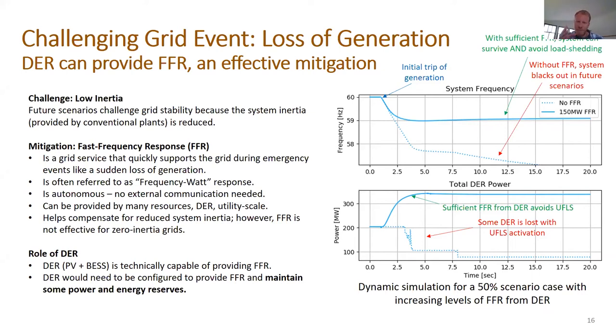In order to illustrate this, Joe, if you look on the right, there are two traces, and we'll just focus first on the blue dotted trace. This is one of the challenging scenarios we studied where there was a sudden loss of generation, which sends frequency down from 60 hertz, plummeting quite quickly over the span of a handful of seconds. You can see that the dotted blue trace goes down and continues going down and essentially indicates a loss of stability of the grid and a grid-wide blackout. That is because the grid was attempting to recover but could not recover in the time required given the system condition. What we applied here was what we call fast frequency response, or FFR.